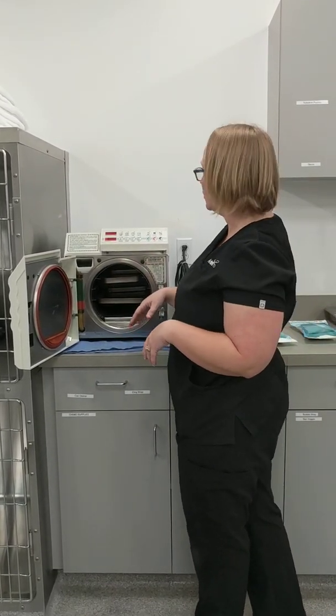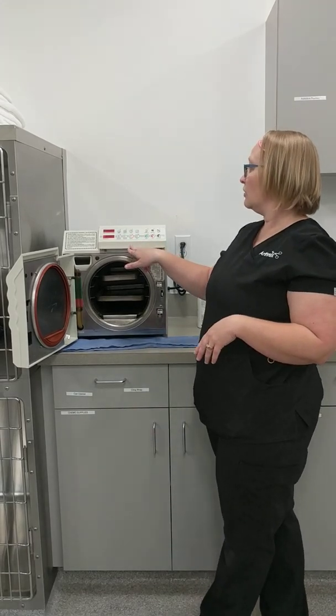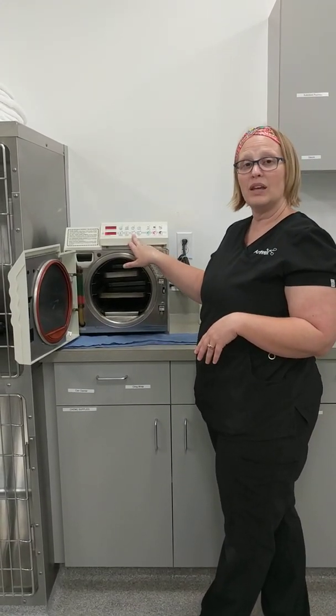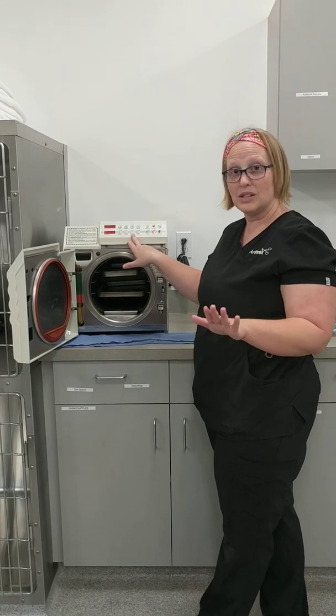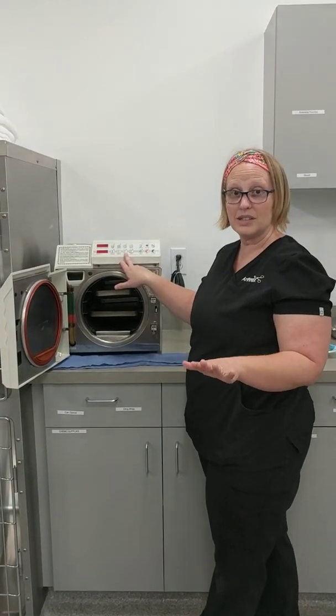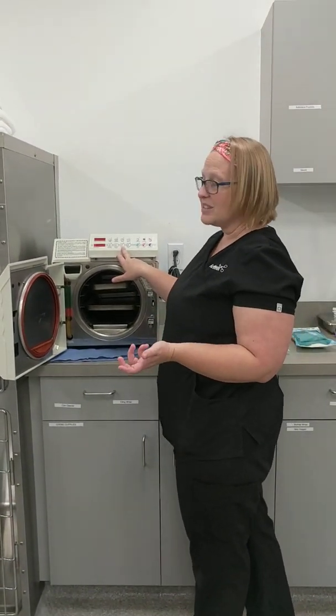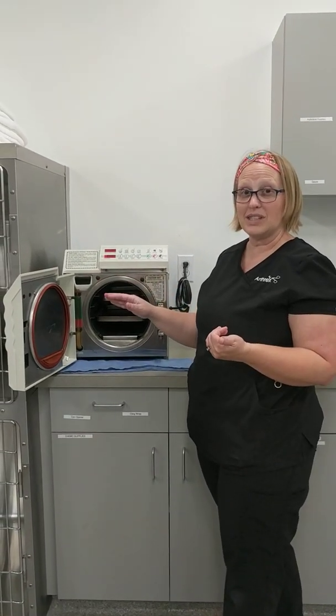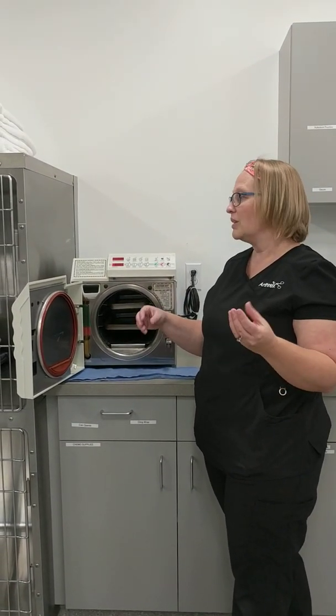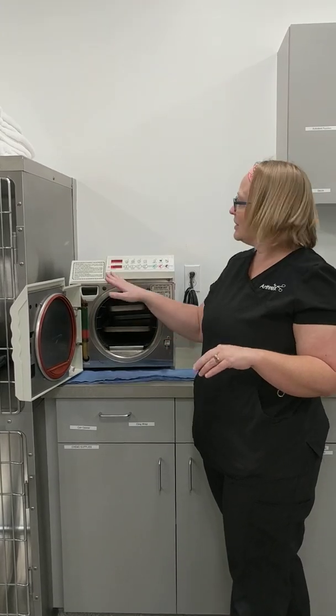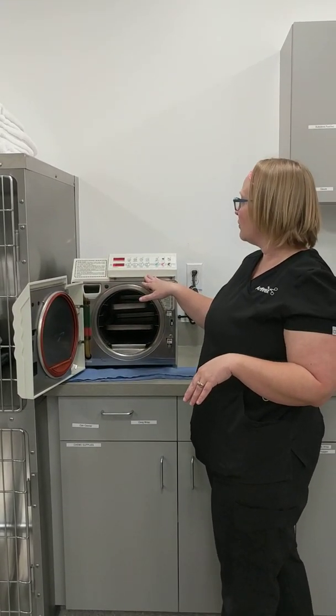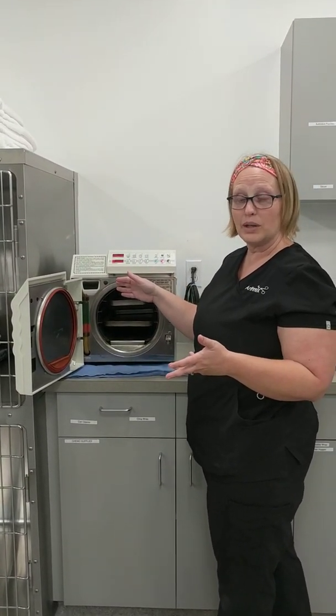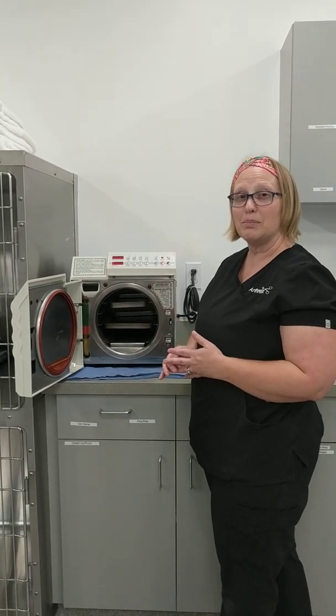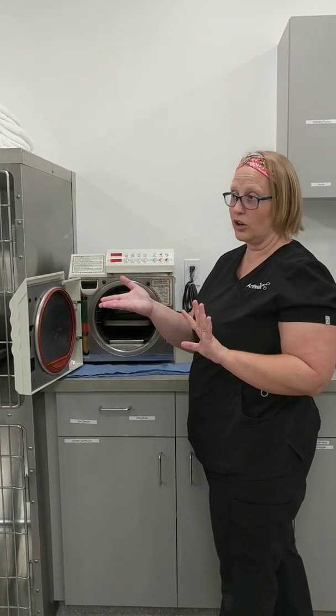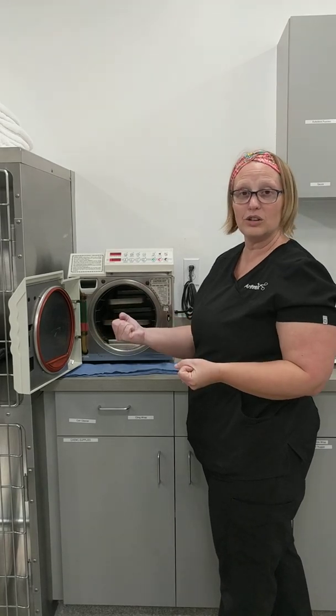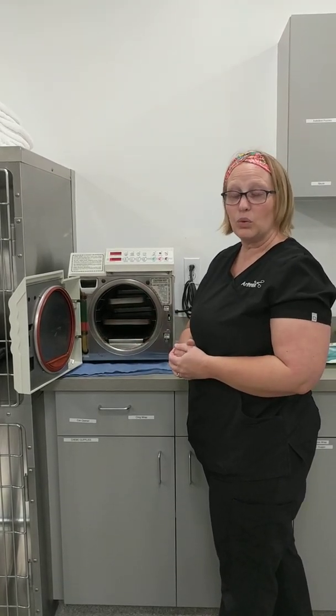The other feature you need to understand, we don't do a lot of liquids in here at all. We don't sterilize liquids. It's not a setting we use here, so I'm not going to discuss that option. Hand pieces for dental, we do have to manually set the temperature. We run it at 270, but it's not a preset button here. I actually have to do an override for the system to do that.